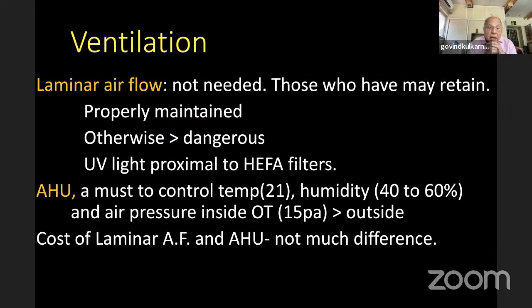Now, an air handling unit is a must to control temperature at 21 to 23 degrees centigrade, humidity 40 to 60 percent, and air pressure inside the OT should be more than outside. All these are done by the AHU. Therefore, whether you use laminar airflow or you don't, the AHU must be there. And therefore, the cost of laminar airflow is not much of a difference, but the maintenance is bothersome.